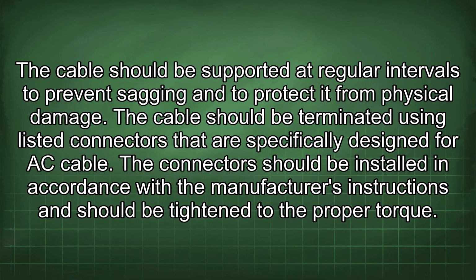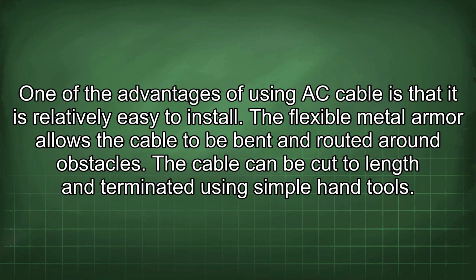The connectors should be installed in accordance with the manufacturer's instructions and should be tightened to the proper torque. One of the advantages of using AC cable is that it is relatively easy to install. The flexible metal armor allows the cable to be bent and routed around obstacles. The cable can be cut to length and terminated using simple hand tools.